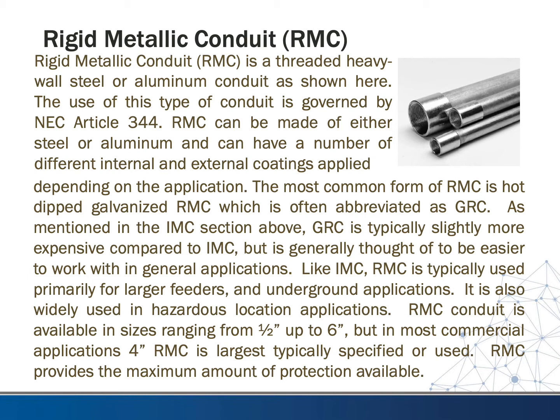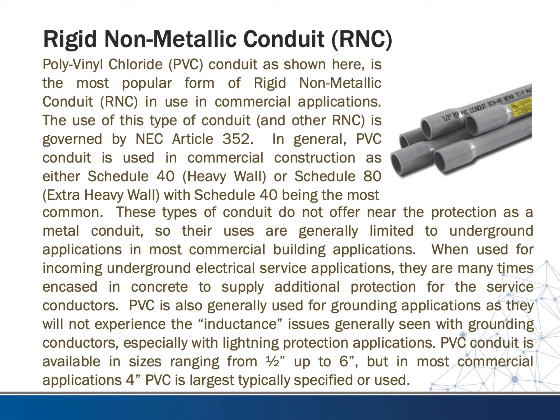Rigid metallic conduit, or RMC, is a threaded, heavy-wall steel or aluminum conduit. Its use is governed by NEC Article 344. RMC can be made of steel or aluminum and can have various internal and external coatings depending on the application. The most common form is hot-dipped galvanized steel RMC, often abbreviated as GRC. GRC is typically slightly more expensive than IMC but is generally considered easier to work with. Like IMC, RMC is primarily used for larger feeders, underground applications, and hazardous location applications. It is available in sizes from half-inch to six-inch, with four-inch being the largest typically specified. RMC provides the maximum amount of protection available for conductors.